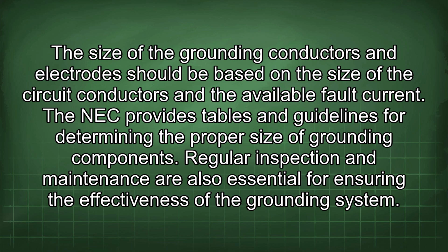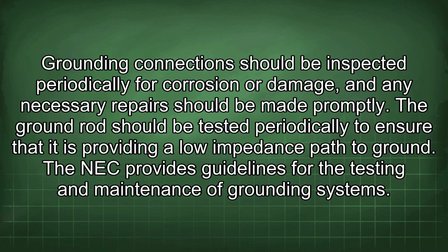Regular inspection and maintenance are also essential for ensuring the effectiveness of the grounding system. Grounding connections should be inspected periodically for corrosion or damage, and any necessary repairs should be made promptly. The ground rod should be tested periodically to ensure that it is providing a low impedance path to ground. The NEC provides guidelines for the testing and maintenance of grounding systems.